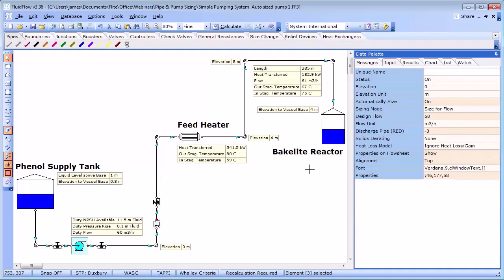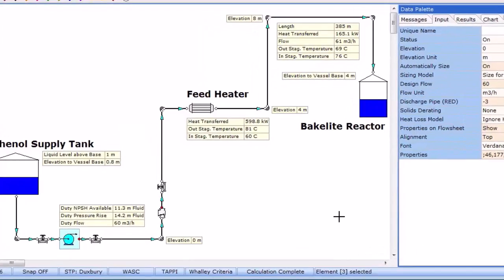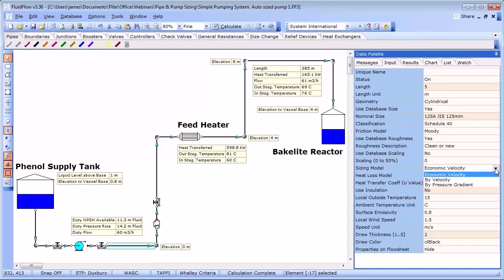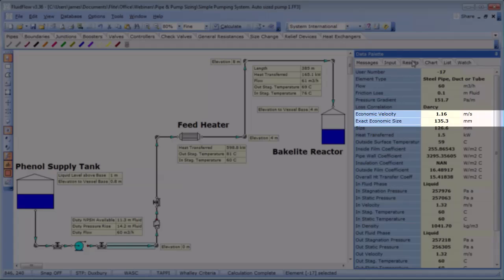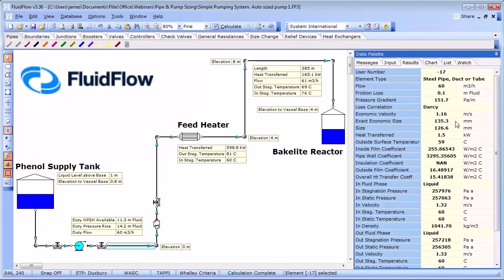Often a good starting point is to size the pipe work using economic design criteria. Economic design criteria considers maintenance costs, energy costs, installation costs, operating frequency of the system etc and these parameters are different for different pipe materials. And before we size the pipe work we should decide the mechanism we are going to use to deliver the 60 meter cube per hour of phenol. We basically have two options available: use a flow control valve or other throttling device or we can use a variable speed drive on the pump. We will choose a variable speed pump in this case. We have a number of options to choose from to automatically size our pipe work including economic velocity, a design velocity or design pressure gradient. We are going to choose economic velocity as we wish to develop an economic system design.